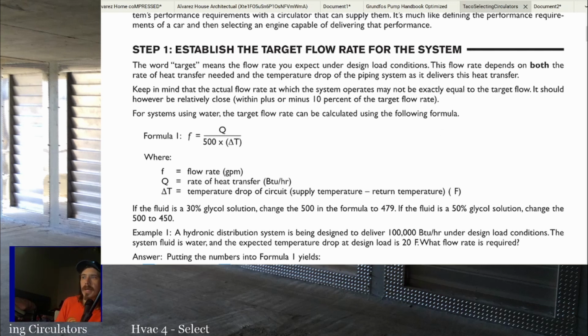And that comes up a lot in our trade, right? Plus or minus 10% on voltage, plus or minus 10% on airflow, CFM delivered to individual rooms, and depending on your system, you're going to see plus or minus 10%. That's what we're trying to get to. We don't have to be exact, but we want to be plus or minus 10% when we design it. So for systems using water, the target flow rate can be calculated using the following formula.